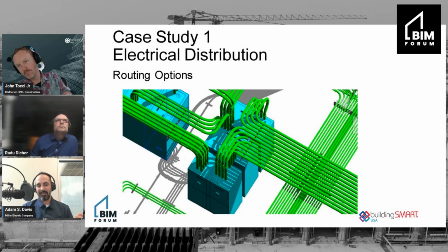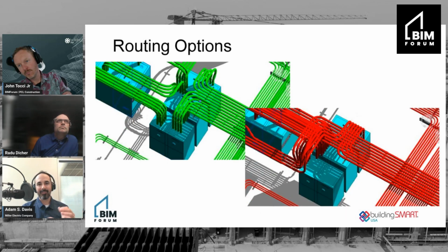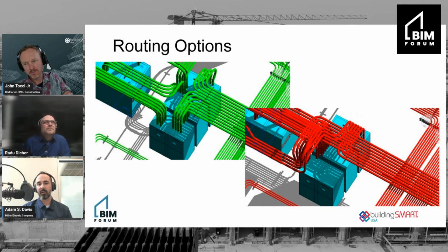However, it wasn't the beginning, and I'll share some of the tools, right? So here's a side-by-side iteration of what we did. The red version here was one of our first tries at it. Then we had to get more specific about the no-go zones, the equipment tags, and the locations of the gear that we needed all of these conduits to go inside of. You can see that here in the red version. It looks kind of like a waffle. I like to call that the waffle. And on the left side, you can see we got a little bit better, not perfect.